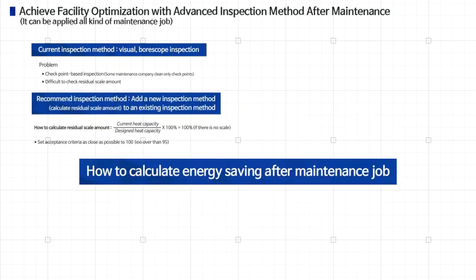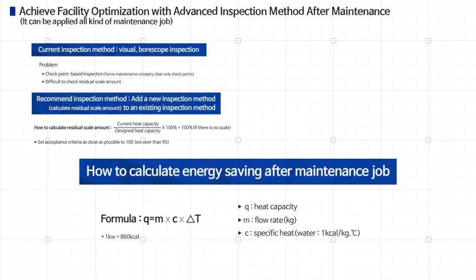Next is how to calculate energy saving after maintenance. You can calculate it easily with the heat capacity formula Q equals m times c times delta T. In this formula, Q means heat capacity, m means flow rate, C means specific heat of fluid, and delta T means temperature variation before and after maintenance.